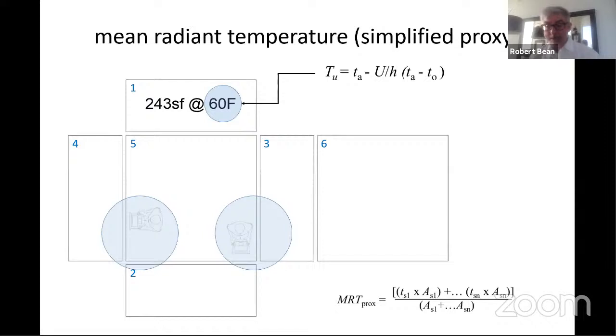But what we're looking at in the simplest form is a weighted average. There's basically three ways of doing it, the weighted average method. And all we're doing here is taking the area with the temperature, and we can calculate that temperature with a very simple formula that you see there. So it's the air temperature in the space, which is reduced by the U value, which we can calculate, divided by the H, which is a convective coefficient, which is modified by a temperature differential between the air temperature and the outdoor temperature. So if we know what the U value is, which we can calculate based on the architecture, and we know whether the surface is vertical or horizontal, and we know what the outdoor temperature is and what our design temperature is, we can actually calculate that inside surface temperature.